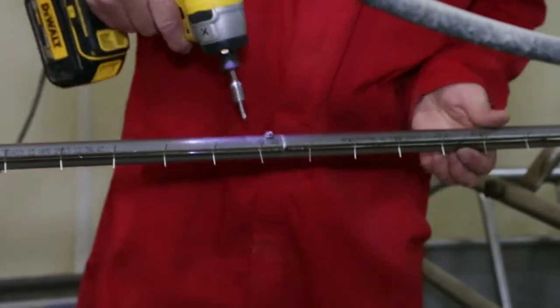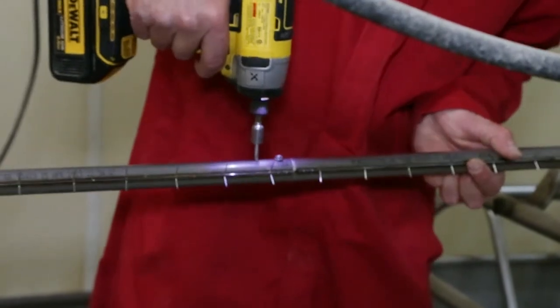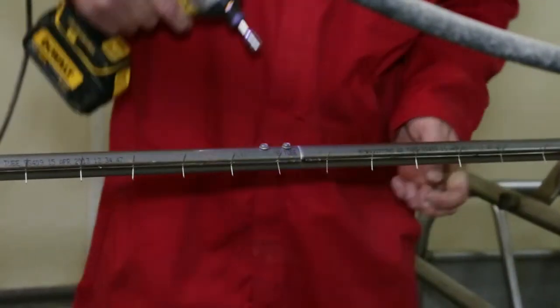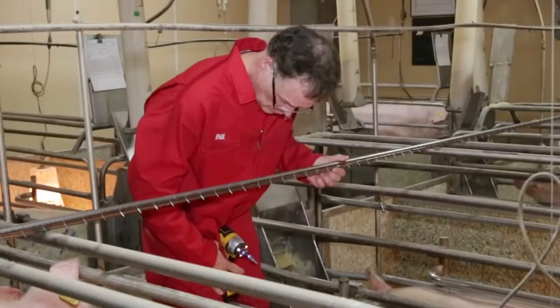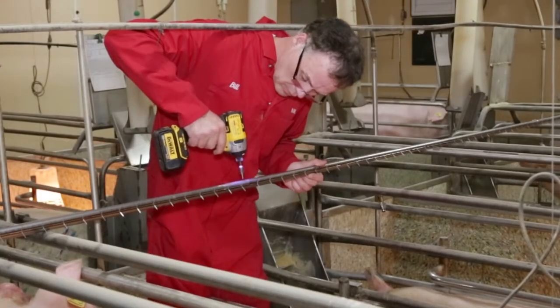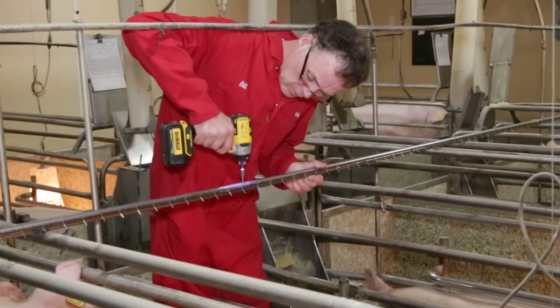Each swedge joint must have two self-tapping screws for maximum rigidity. If needed, use a small punch, make two small dents into the pipe at the location of the self-tapping screws. The dents will help guide the screws. Take care not to bend or damage the corona points welded to the pipes.